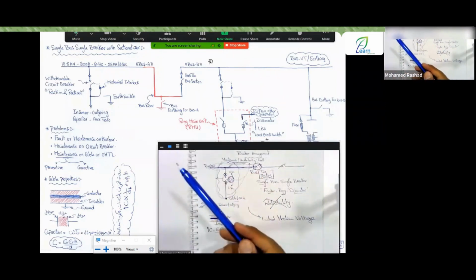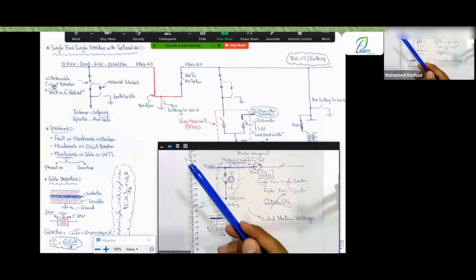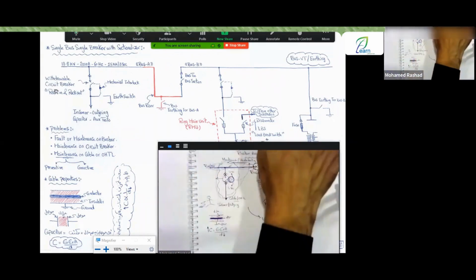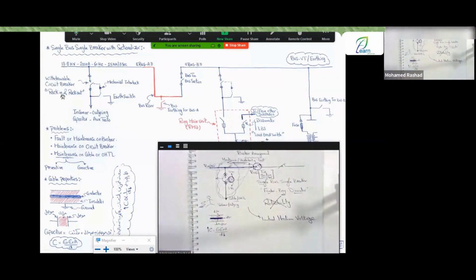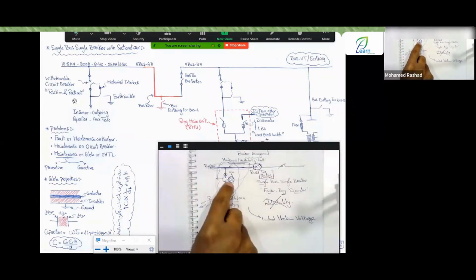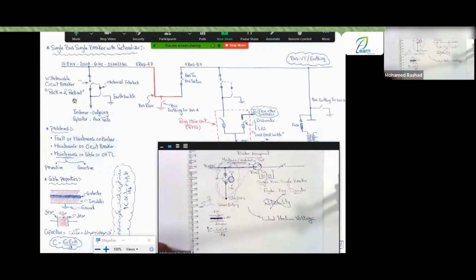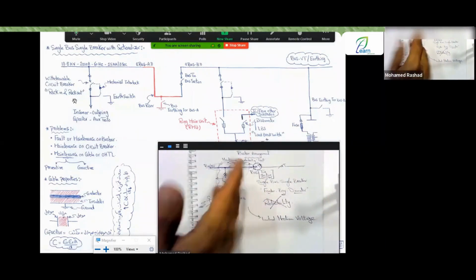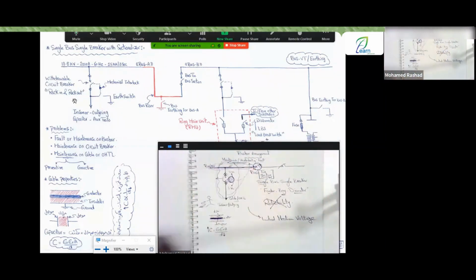Look up here with me so I can show you with the mouse. Here it is, a withdrawable circuit breaker. What does withdrawable mean? It means you can make it rack in or rack out. Rack in means going inside and rack out means going outside. So this is rack in or rack out, meaning you can insert or remove the breaker like a drawer. Therefore, in the case of breaker maintenance, I can pull it out, rack out, and perform maintenance on it without affecting the rest of the connected loads.